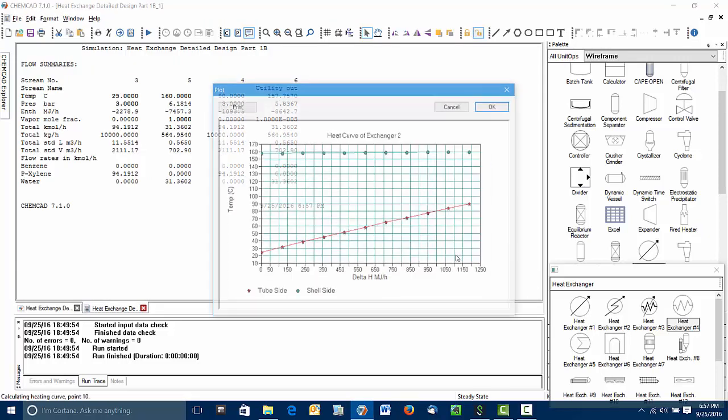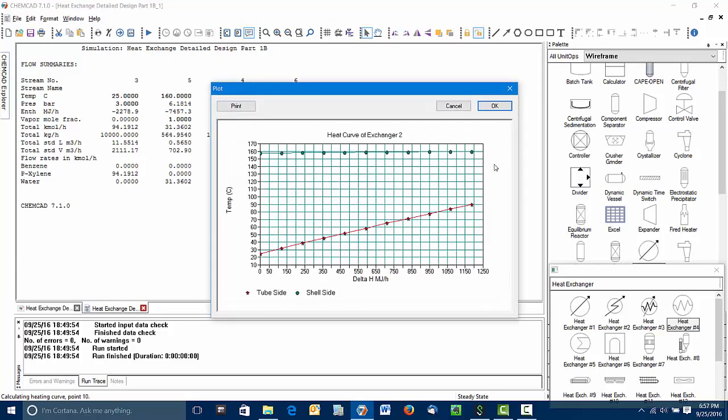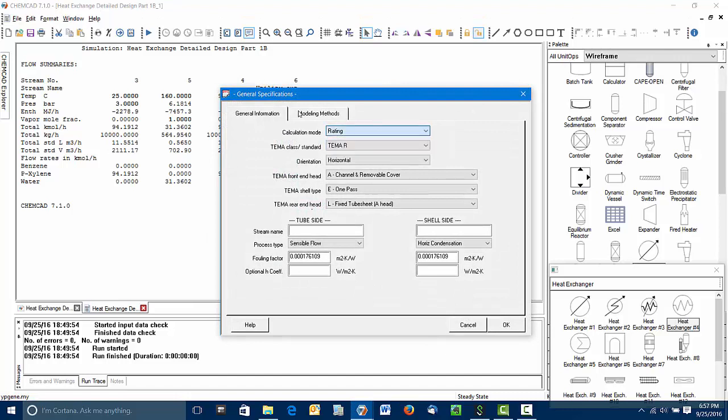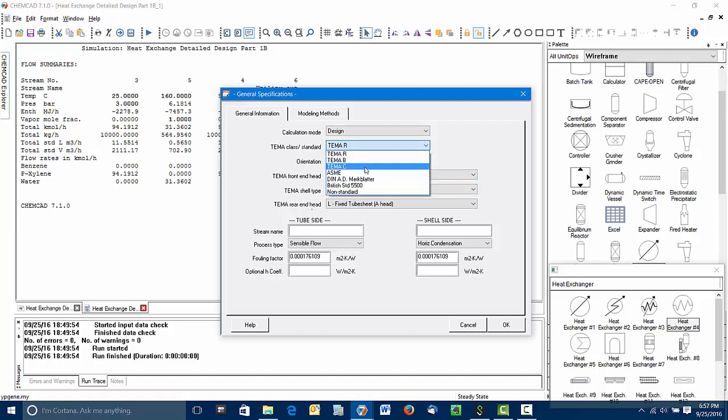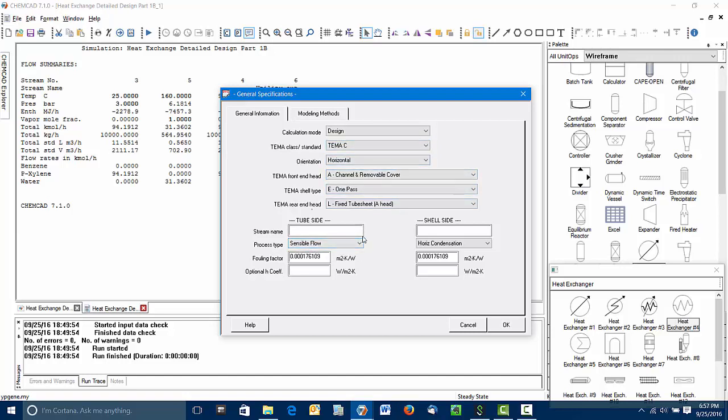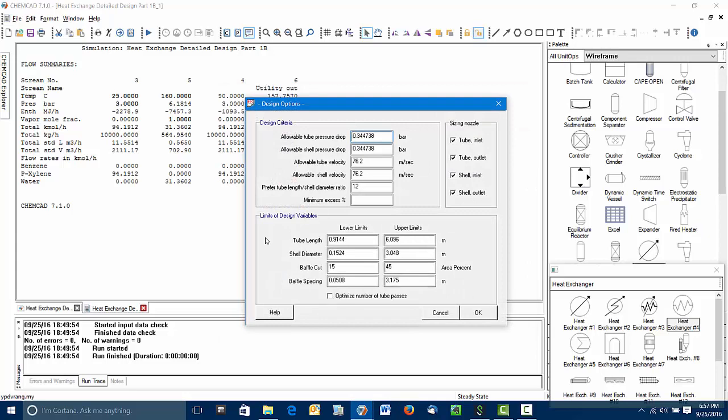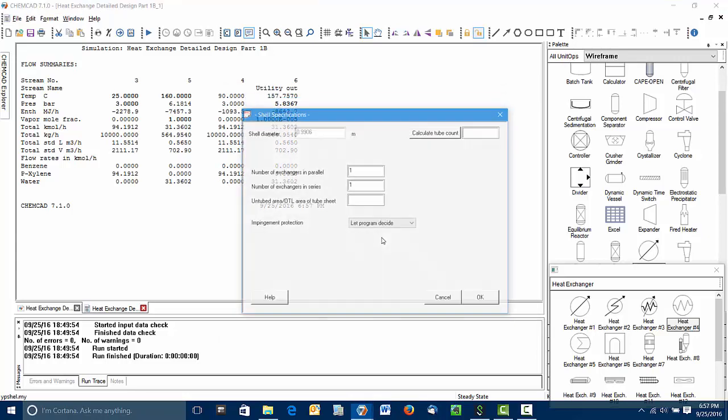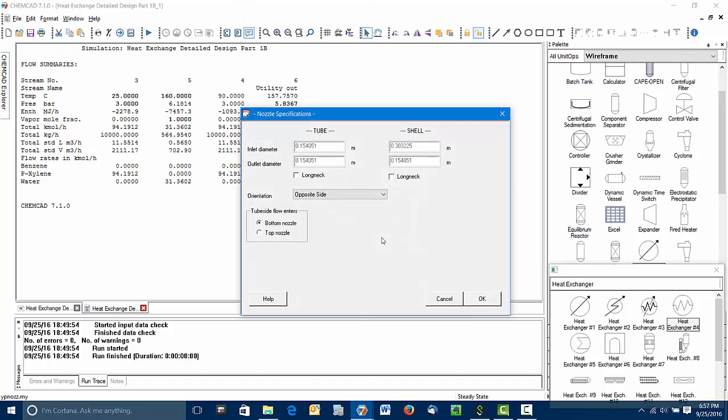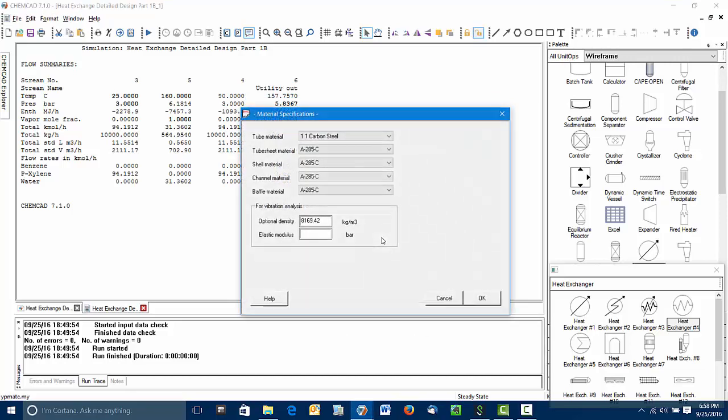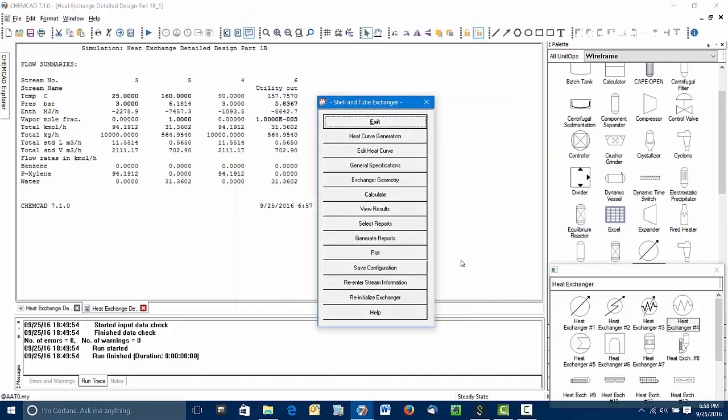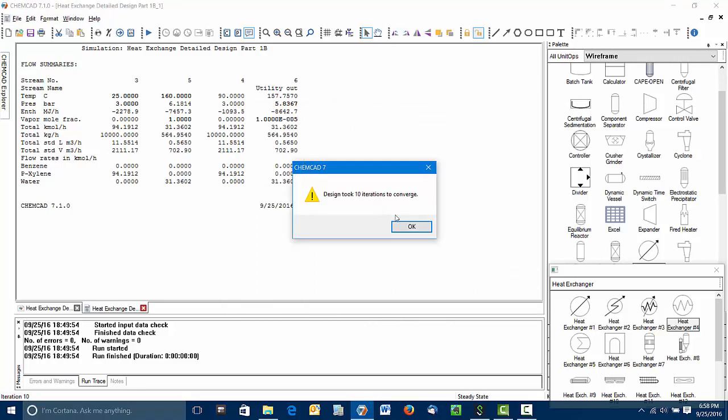ChemCAD again generates the heat curve. You can see the steam coming in at 160, leaving a little bit lower than 160. That's because of the pressure drop on the shell side of the exchanger. But that all looks good. Remember we put this into design mode. We'll go with a TEMA C exchanger again. One pass. You can see it's caught sensible flow on the tube side and horizontal condensation on the shell side. Again, we'll optimize the number of tube passes. And let it calculate the exchanger.